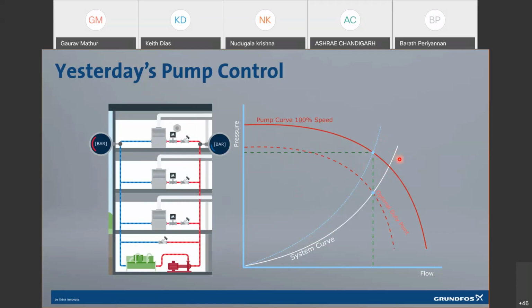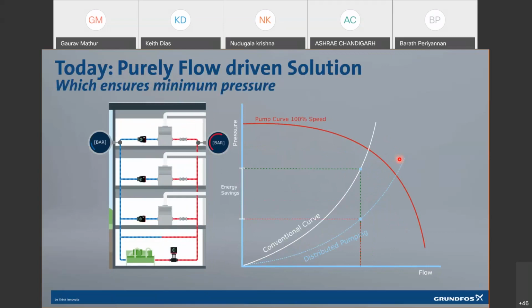Based on this changing system curve, we are able to achieve the savings by moving the set point to make sure that we achieve the flow requirement in the most optimum way. But as you can see, the way this white curve is moving, you have a conventional system where the pressure keeps on increasing when you have a load happening. Whereas if you look at the system curve in case of a distributed pumping system, it is not moving because there is no throttling happening when you have a distributed pumping system.